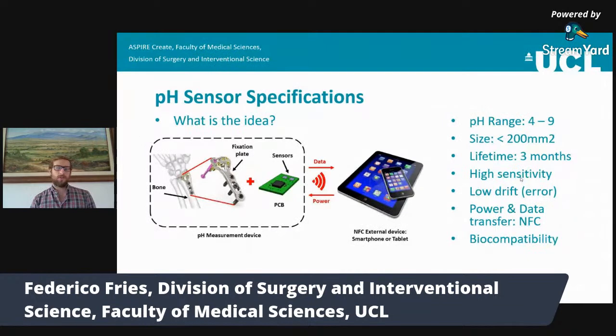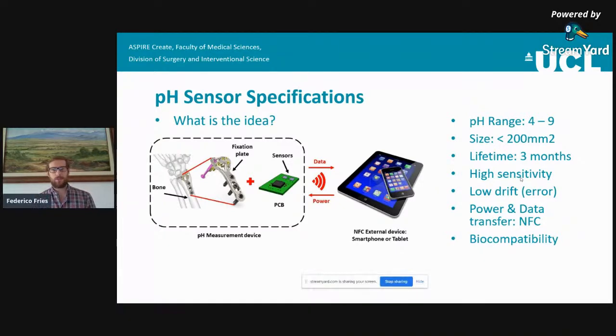Low drift is also important. Drift is an error that many electronic devices and sensors have. For instance, with a drift error of 0.1 pH per hour, if you're measuring a solution with 7 pH, after one hour you get 7.1, then 7.2, 7.3, and so on. If you measure for 3 months, you'll have a huge error that saturates the sensor.